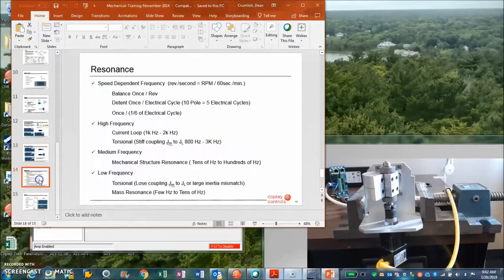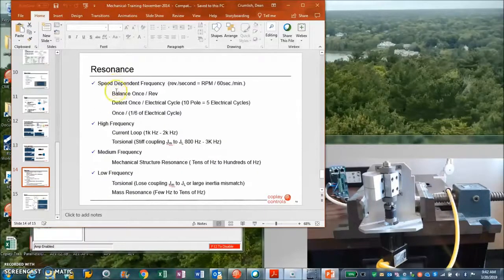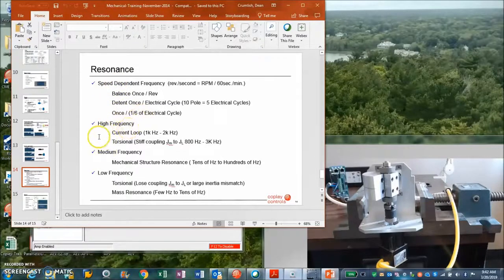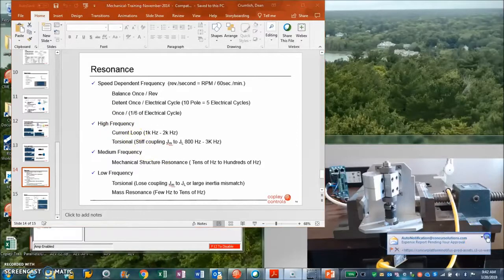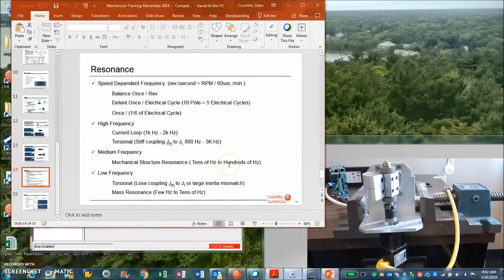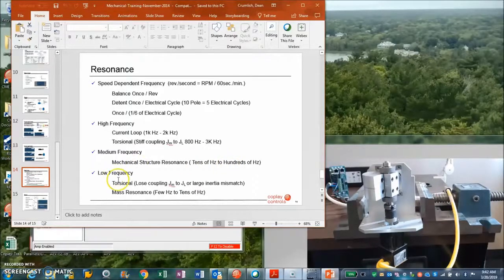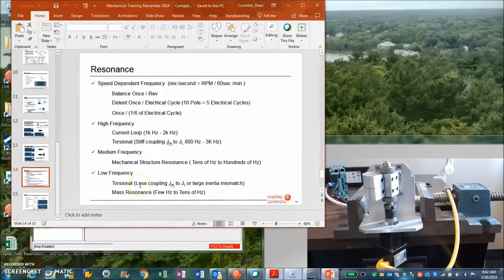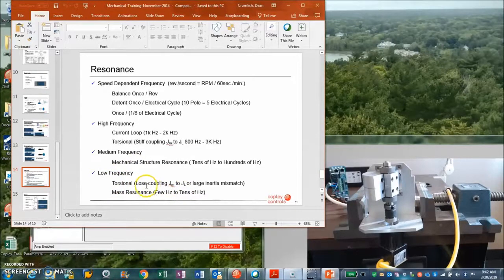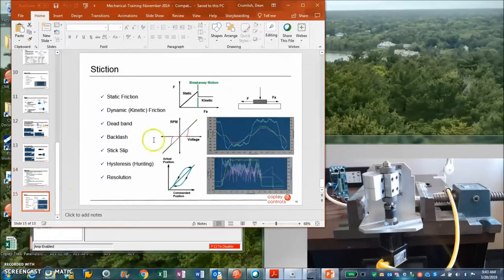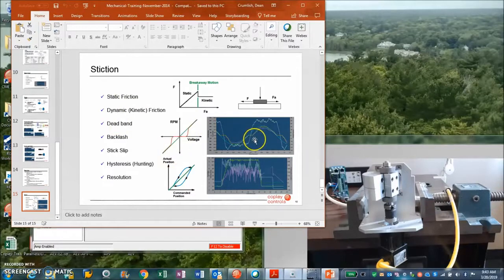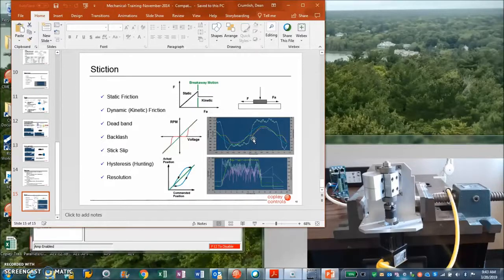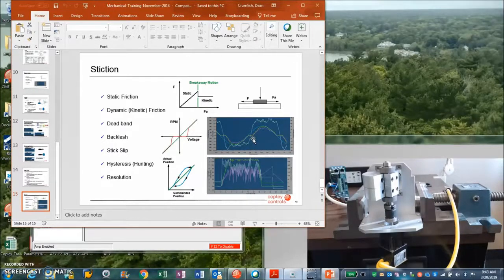If you have a system with resonance, you look at what frequency it is. High frequencies close to the current loop or the torsional resonance, mediums are like mechanical structures. 120 hertz is interesting because that's rectified line, and so is 60 hertz. But low frequencies in the tens of hertz—it could be like the electromechanical system, it could be a large mass that's bouncing.